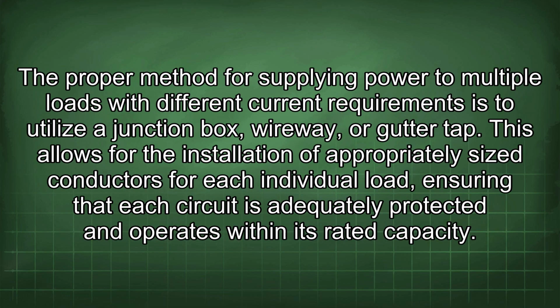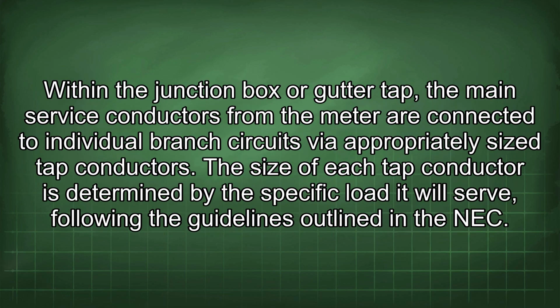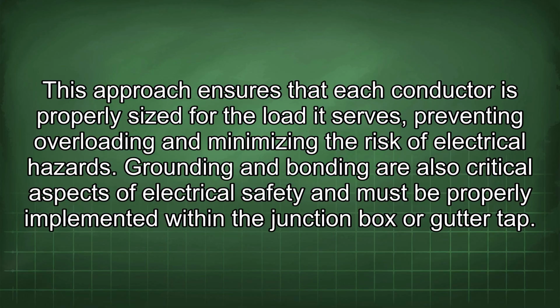The proper method for supplying power to multiple loads with different current requirements is to utilize a junction box, wireway, or gutter tap. This allows for the installation of appropriately sized conductors for each individual load, ensuring that each circuit is adequately protected and operates within its rated capacity. Within the junction box or gutter tap, the main service conductors from the meter are connected to individual branch circuits via appropriately sized tap conductors. The size of each tap conductor is determined by the specific load it will serve, following the guidelines outlined in the NEC. This approach ensures that each conductor is properly sized for the load it serves, preventing overloading and minimizing the risk of electrical hazards.